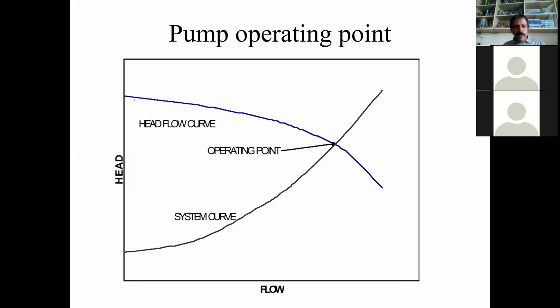Now the operating point is where your pump curve meets the system curve. That is this point. So this is our system curve, and this is going to be our operating point. We may have several pumps in the market which will pass through this point. So the operating pump which will satisfy a requirement is the one which will pass through this point.